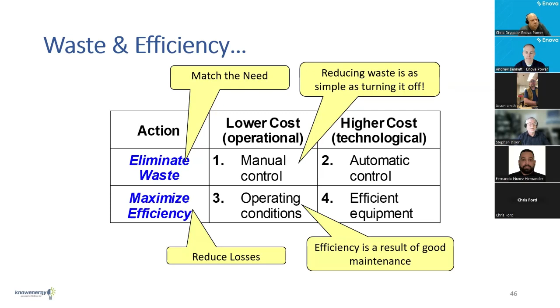Because even the most efficient equipment that we could put in will suffer from the poor operating conditions that it might be exposed to. Things like this. And these are real pictures from real energy hunts that we've done, right? So here we see a condenser with coils that are plugged. Here we see the other side of the system, which is the evaporator within a coil, within a ductwork, and it's plugged quite nicely. Just one second.